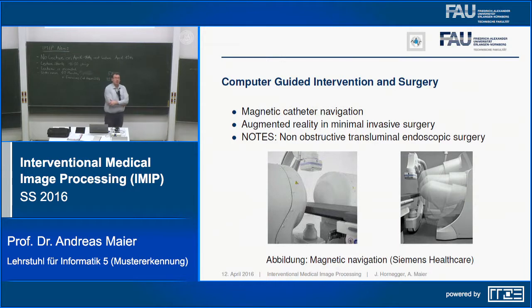Another thing that is very useful for intervention are guidance systems. This is a very cool device — a magnetic catheter navigation system. What you see here is a C-arm system with a small flat panel detector. Why are we using a flat panel detector? Well, we have a huge magnet here that can induce a huge magnetic field. If you attended DMIP, you know why we are using a flat panel here — we are not using an image intensifier, because it won't work in such a high magnetic field.